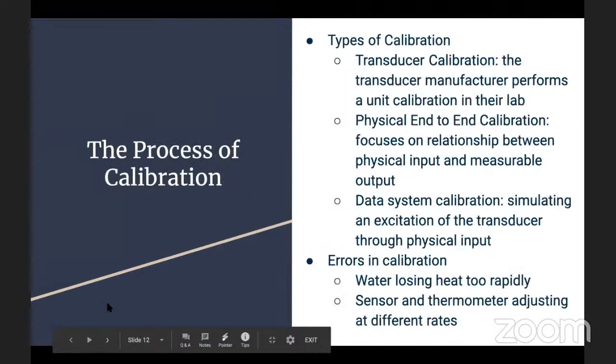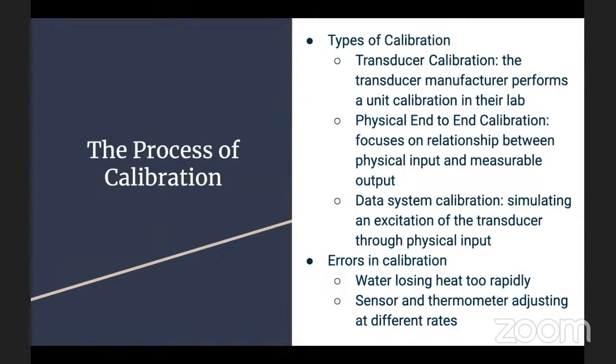You also need to know about the process of calibration. There are a couple types of calibration. One type is transducer calibration - the transducer manufacturer performs a unit calibration in their lab. You can also do physical end-to-end calibration. There's also end-to-end calibration that focuses on the relationship between physical input and measurable output. There's also data system calibration, which is simulating an excitation of a transducer through physical input.